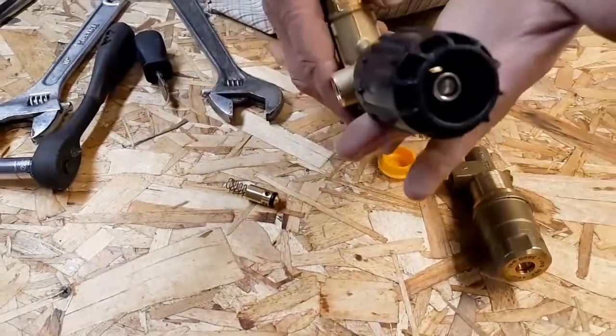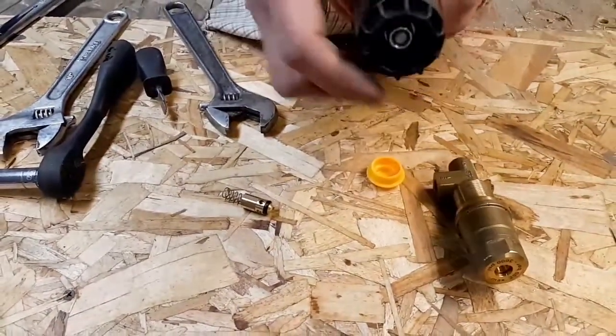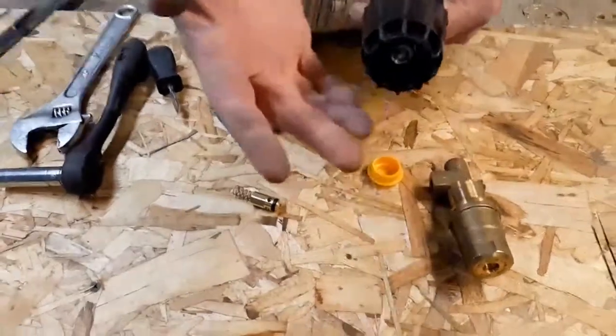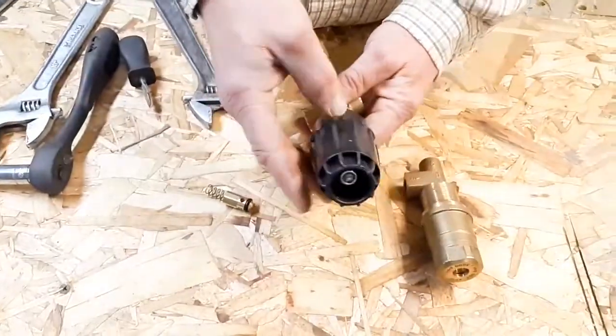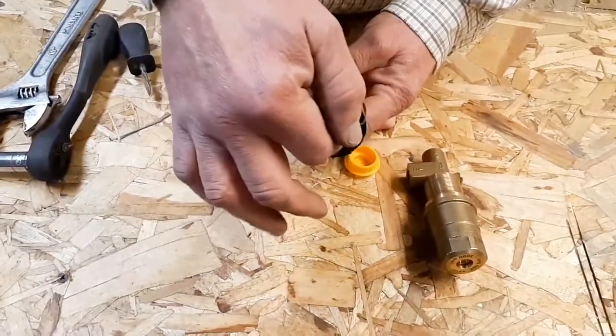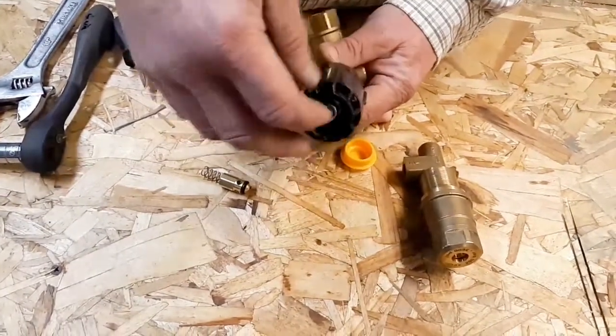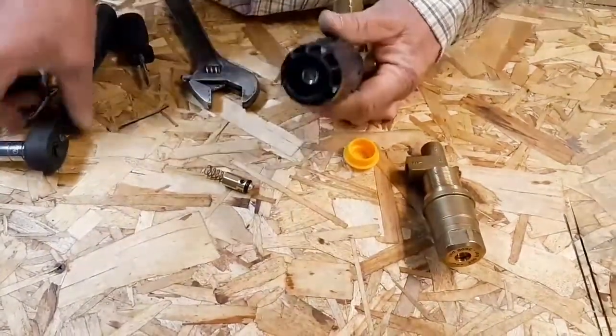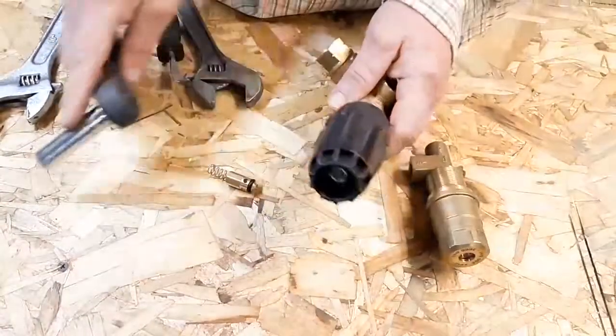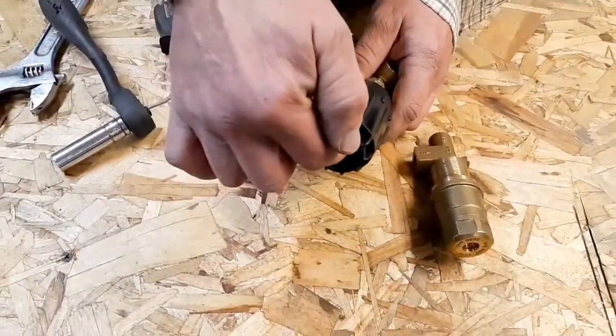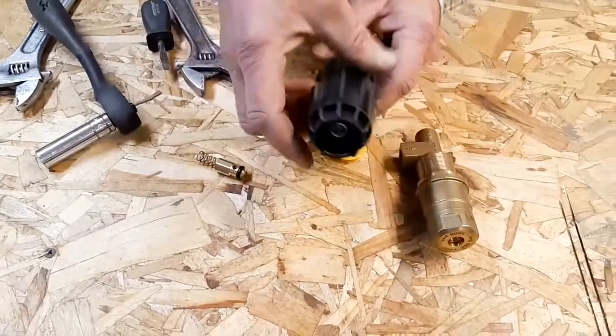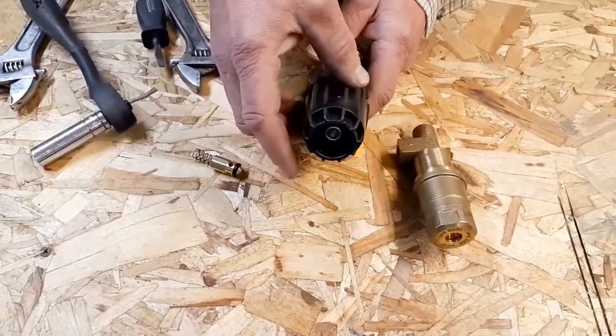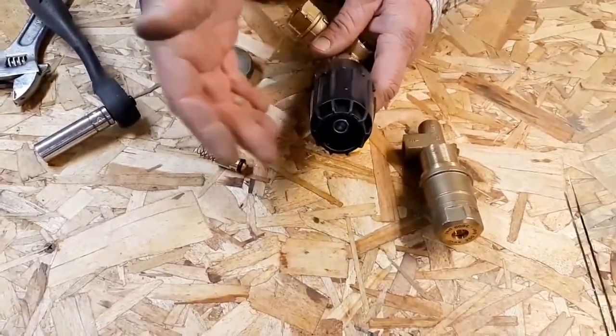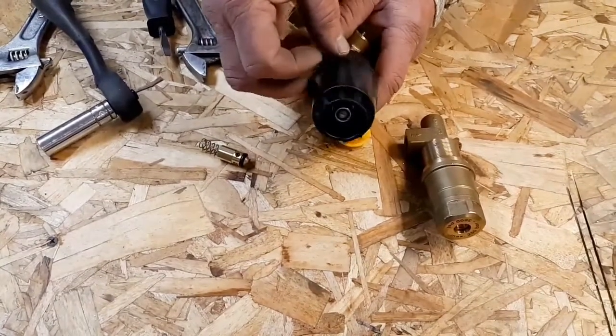Inside of there, you've got a nylock nut. That's to help prevent this from coming off. Also, it helps if you're going to set a certain pressure and leave it there - you can tighten that up and this cannot come loose. So even if this comes off, a lot of times when you get these new, that nylock nut is screwed on there a little bit too far, so it's difficult to turn the pressure down as far as you want. Let's say you want to turn it down to 250 psi, but you can't - it'll only go down to 400.